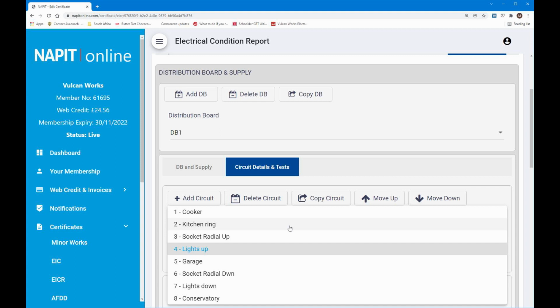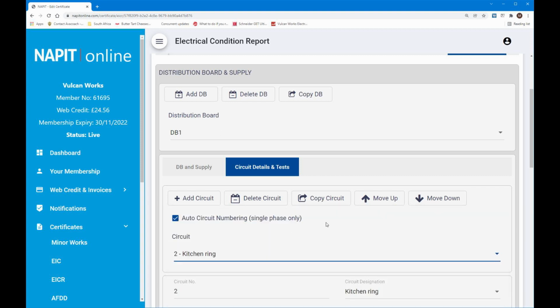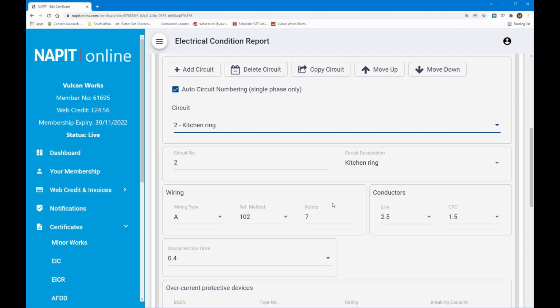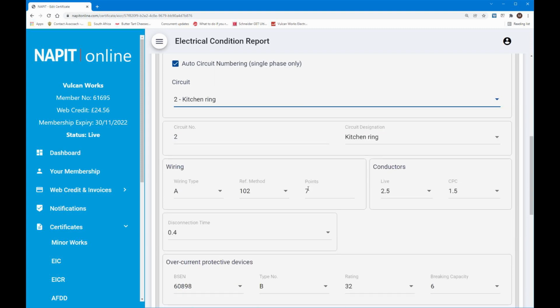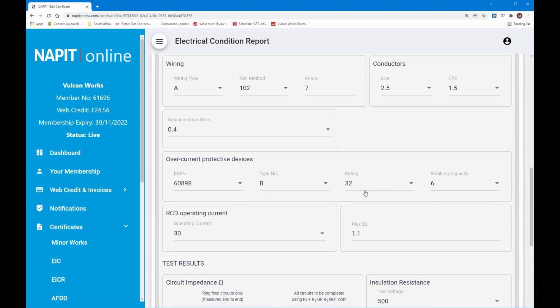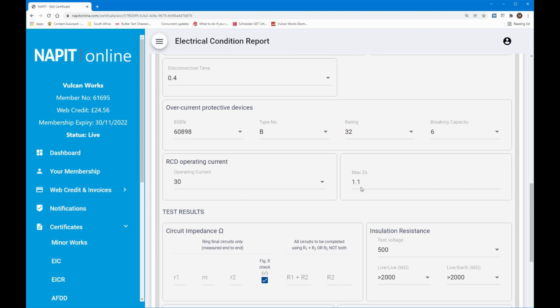Okay, let's go back to the kitchen ring, because this is a little bit more involved. So first of all, let's go through the bits that we've been able to do. So the wiring type A, the method was 102. Now I put down 7 points. There were 4 in the kitchen, 3 in the other part of that room where the sofa and the TV were, where I think they are part of a spur from the ring. So there were 7 points in total. They're definitely on the same circuit breaker. Anyway, 2.5mm conductors, 1.5 CPC, disconnection time 0.4, type B, 32 amp rating with a 1.1 maximum ZS.